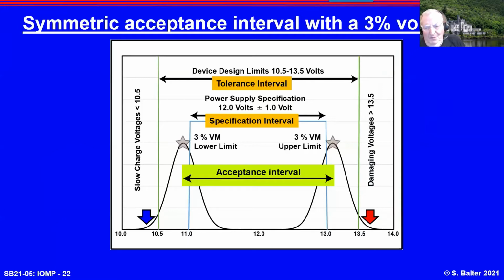because I have a good voltmeter, I can actually accept with these 2%, 2.5% on each side, differences, voltages in the range shown. So I can accept a little less than 11 volts, a little more than 13 volts, provided I'm willing to accept that I'm exceeding the tolerance intervals on the two sides. Part of your professional judgment is to look at those arrows and decide if they are appropriate to your purpose.